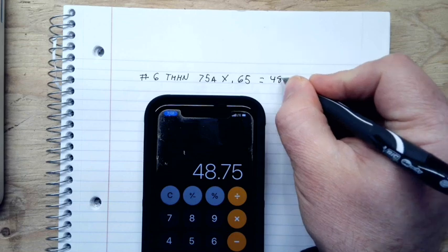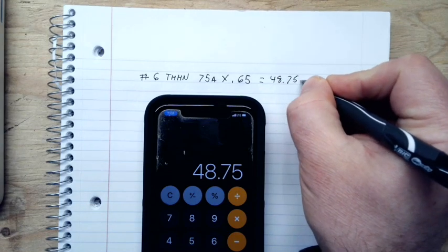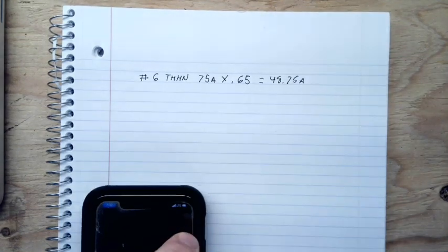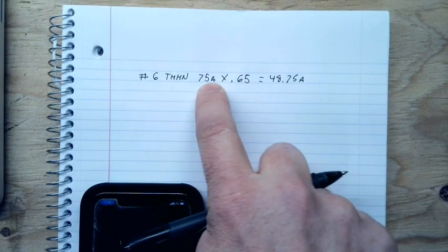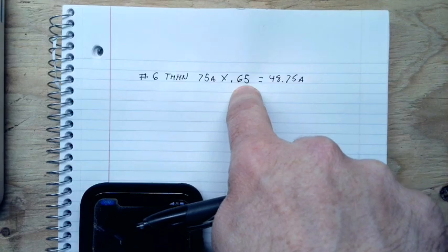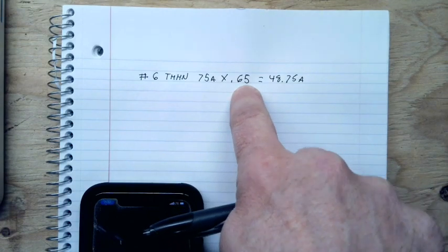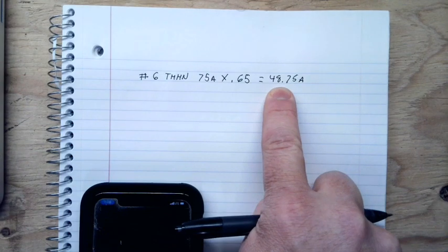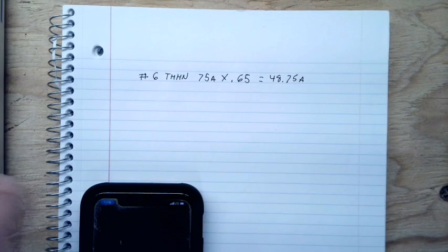Going with 75 amps times 0.65 equals 48.75 amps. Okay, so we've reduced this number 6 wire, which is good to 75. But because it's being run in a hot temperature or a hot ambient temperature, we have to reduce it. So now it's only good to 48.75, not good enough for what we need. So now we need to upsize the wire. So we're going to go from a number 6 to a number 4.